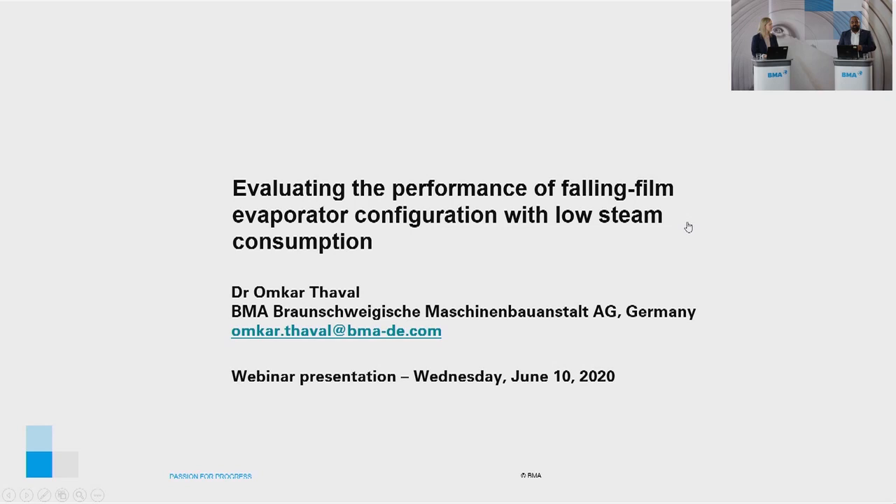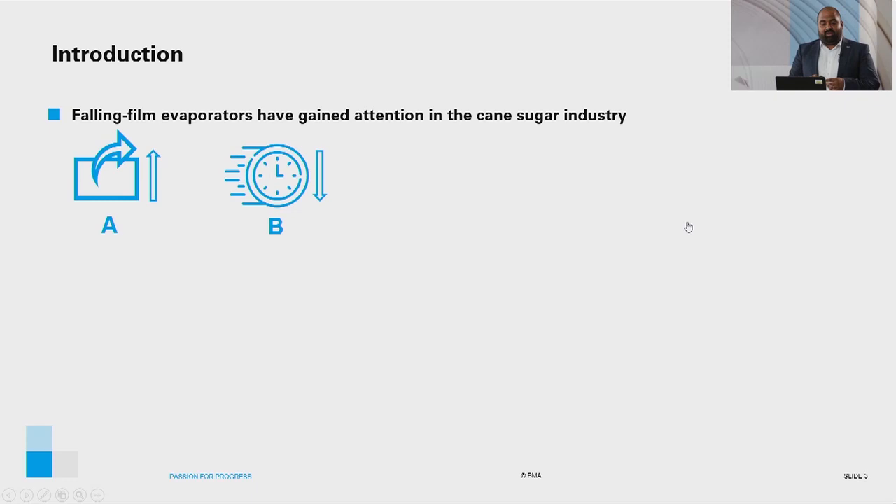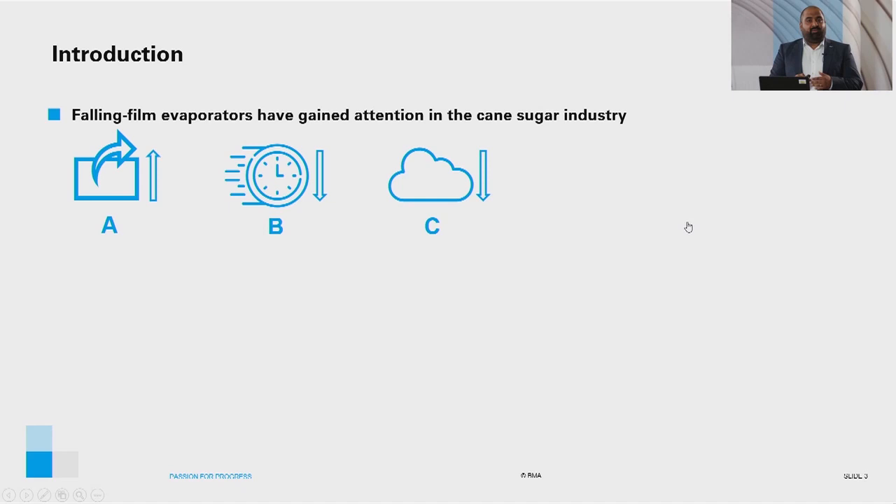Falling film evaporators have gained attention in the cane sugar industry owing to the high heat transfer coefficient, the longer operating time between cleans, and the possibility to reduce exhaust steam consumption. Few other attractive features include the ability to operate at lower temperature differences and shorter juice residence time in the evaporator, limiting the extent of sucrose degradation.